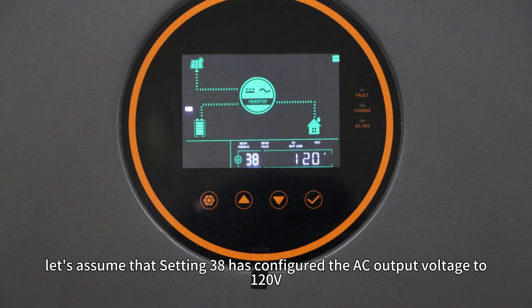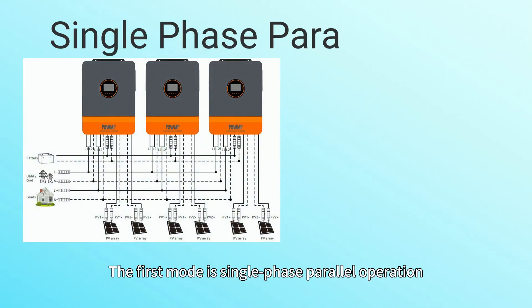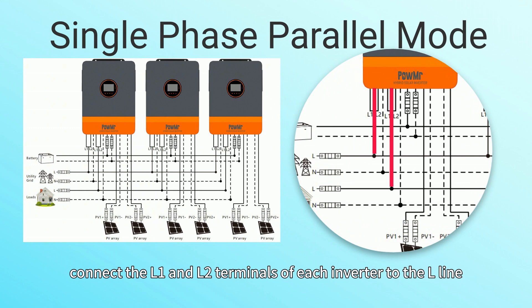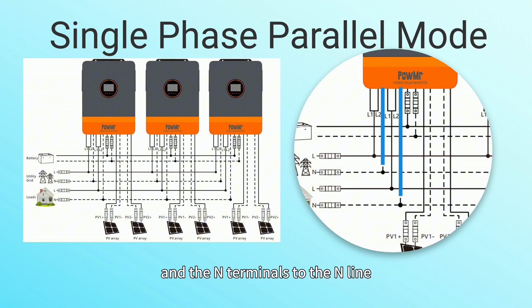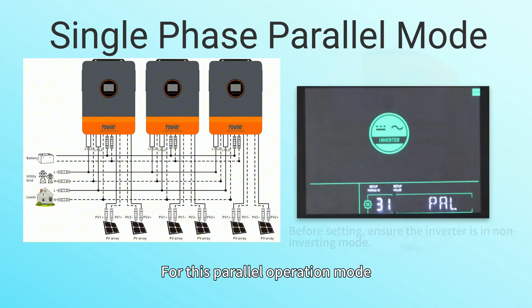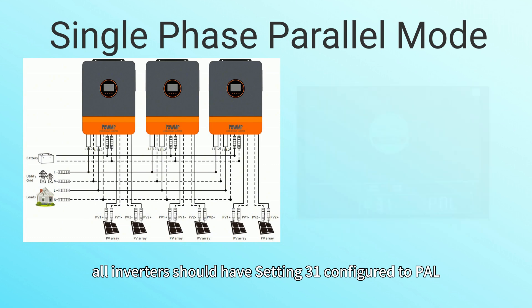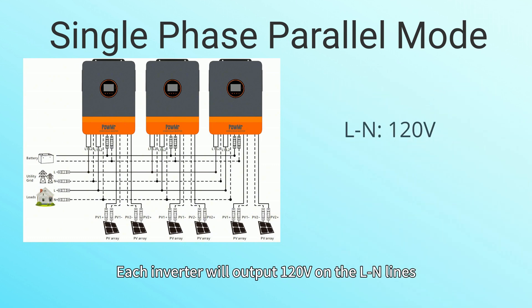Before we begin, let's assume that setting 38 has configured the AC output voltage to 120V. The first mode is single-phase parallel operation. In this mode, connect the L1 and L2 terminals of each inverter to the L line and the N terminals to the N line. For this parallel operation mode, all inverters should have setting 31 configured to PAL. Each inverter will output 120V on the L-N lines.